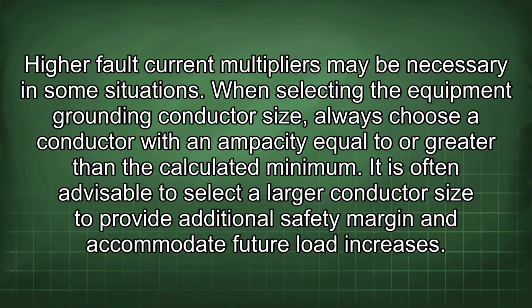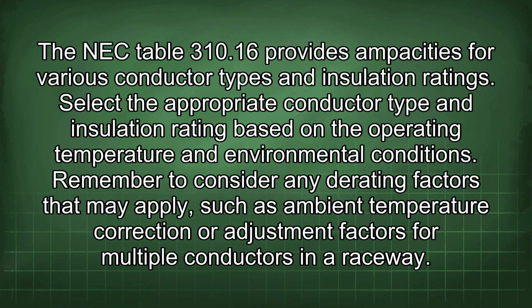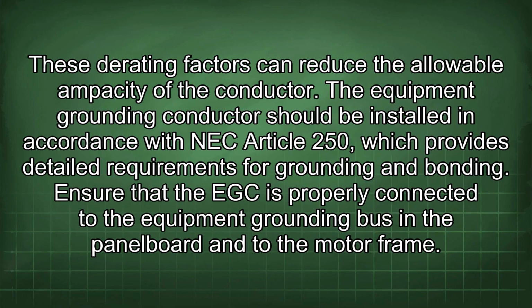The NEC Table 310.16 provides ampacities for various conductor types and insulation ratings. Select the appropriate conductor type and insulation rating based on the operating temperature and environmental conditions. Remember to consider any derating factors that may apply, such as ambient temperature correction or adjustment factors for multiple conductors in a raceway. These derating factors can reduce the allowable ampacity of the conductor.